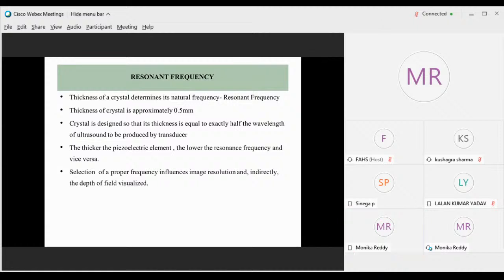The usual thickness of the crystal of a medical transducer is approximately 0.5 mm, and this crystal is designed so that its thickness is equal to half of the wavelength of the ultrasound produced by the transducer. So the thicker the piezoelectric element, the lower the resonant frequency. So if the resonant frequency is high, it cannot penetrate more.